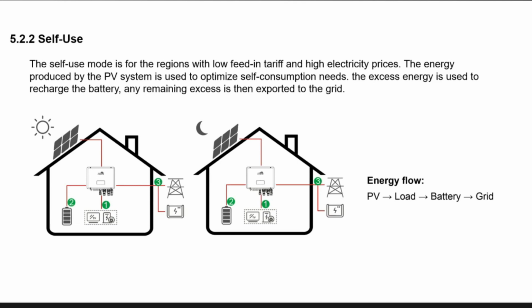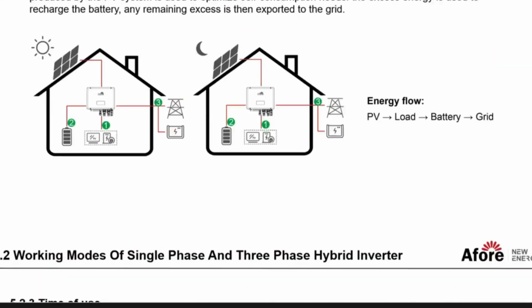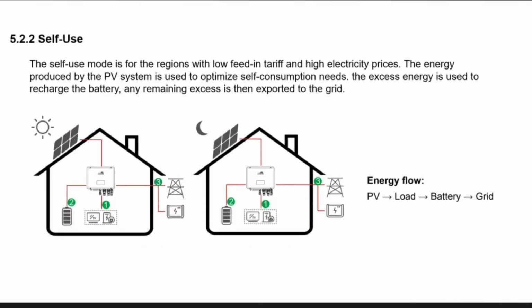The self-use mode is for regions with a low feed-in tariff rate and a high electricity rate. Here is the energy flow. The energy produced by the PV will go to the load first. If the load cannot accept it all, the excess energy will charge the battery. When the battery is fully charged and there is still excess energy, it will go to the grid side. So, check the load.